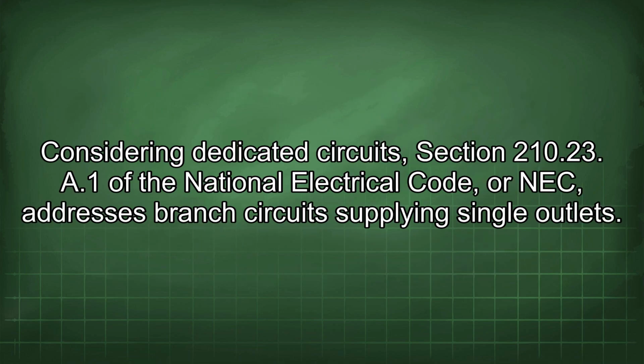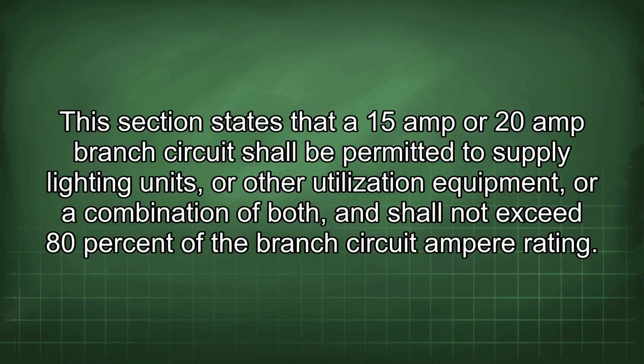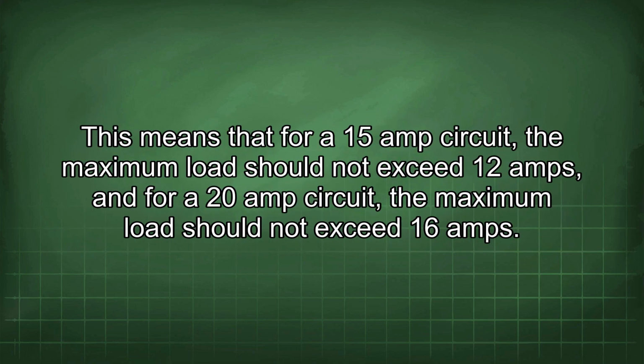Considering dedicated circuits, Section 210.23(A)(1) of the National Electrical Code, or NEC, addresses branch circuits supplying single outlets. This section states that a 15 amp or 20 amp branch circuit shall be permitted to supply lighting units or other utilization equipment, or a combination of both, and shall not exceed 80% of the branch circuit ampere rating. This means that for a 15 amp circuit, the maximum load should not exceed 12 amps, and for a 20 amp circuit, the maximum load should not exceed 16 amps.